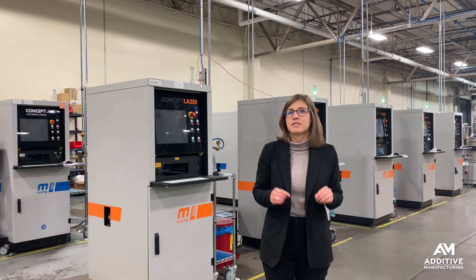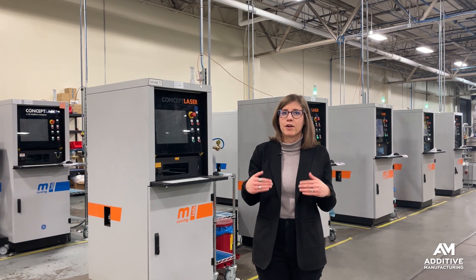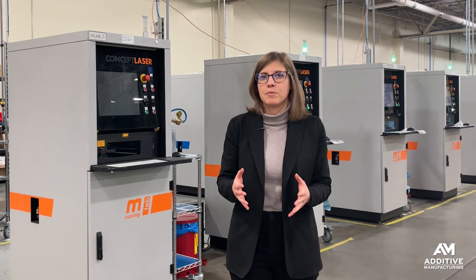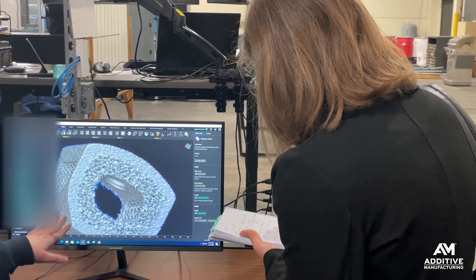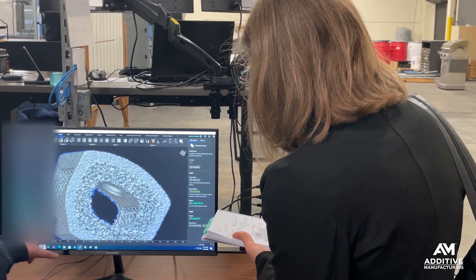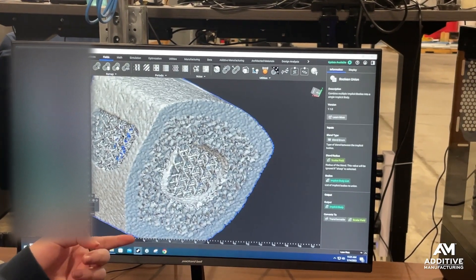They don't design implants here. They're a contract manufacturer, so they receive the designs from their customers, but there's still some engineering work that needs to be done, and that includes manipulating the surface roughness. Using nTopology, they are able to change the depth and the frequency of the roughness to tune it into exactly what the customer wants.